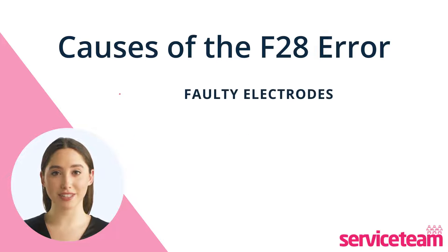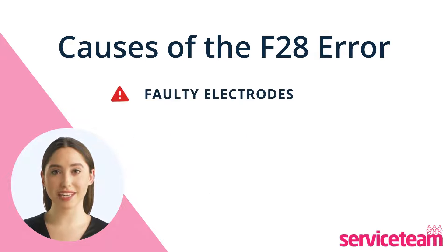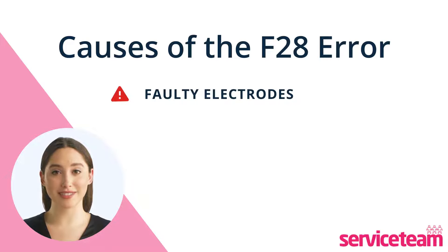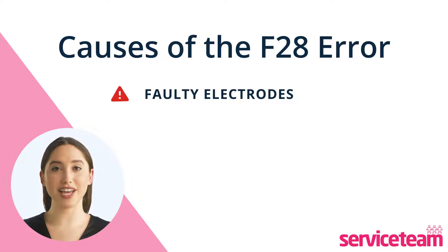Faulty electrodes in the boiler can trigger the F28 fault due to issues with electrical components. These parts can wear out or be affected by moisture and vibrations over time, causing ignition problems.